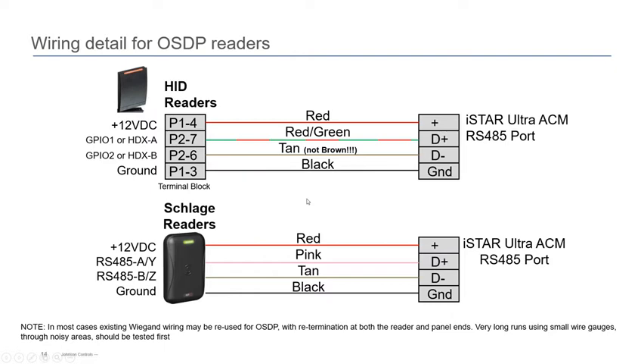The only thing here is that we have had some experience with the HID readers. If you get the pigtail version, there's a tan and a brown, and there's like 15 different colors. A lot of times the brown looks like tan. So if you hook up the brown wire, it's not going to work. You've got to hook up the tan for that, data minus terminal.